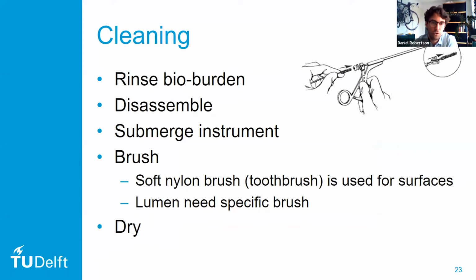Now, you want to use a soft nylon brush on the instruments, and a toothbrush is fine. And you use a brush for the outer surface of the instrument and to get into the mechanism and the tip. Now, for the lumen, so for the long hollow part of the instrument, we need a specific brush that can run right the way through. So when inserted into the back of the instrument, it would reach outside into the tip as well.